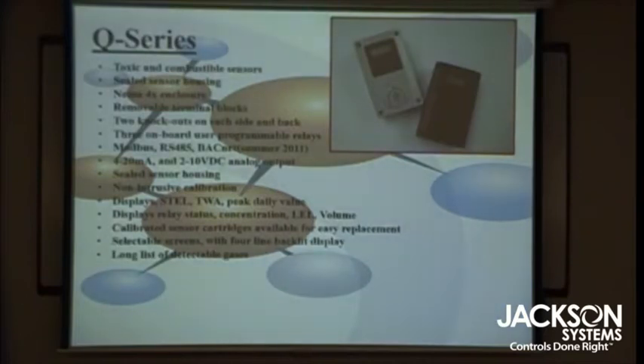It comes in a NEMA 4 enclosure. The enclosure itself, the base of it has knockouts, 2 on each side, 2 on the top and 2 on the back. So if you have to bring your conduit in and out, it's pretty easy for you to configure. The front cover also has a gasket on it, so a rubber gasket. So once you screw it in, it is rated NEMA 4. The sensor housing also is sealed. It screws to the front cover, and there's a rubber gasket there too. So if there's a guy hosing a car or something, he's not going to ruin the electronics by wetting the sensor. It may just ruin the sensor.